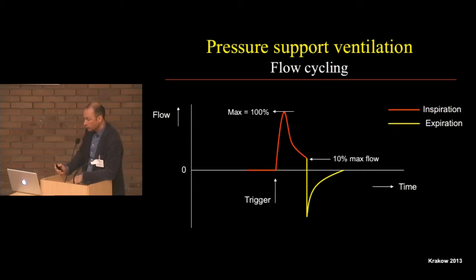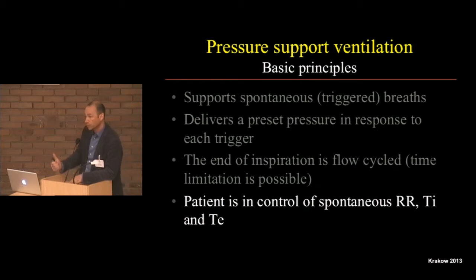Now, during flow-cycled ventilation, this is different. What actually happens is that there's an inspiratory flow, and the machine measures the maximum flow during that mechanical breath, and it sets this maximum flow at 100%. And then as the flow decelerates, you can, as a clinician, choose a percentage. When it reaches, in this case, 10% of the maximum flow, the machine feels that the baby is at the end of inspiration and it will give you an expiration. So this is a different way of cycling off the inspiration. This also means that the patient is in control of not only the respiratory rate, but also the inspiration time and the expiration time. Because the baby can take a quick breath or a very long breath, and the machine will adjust the inspiration time to whatever the baby wants, giving the baby more control.